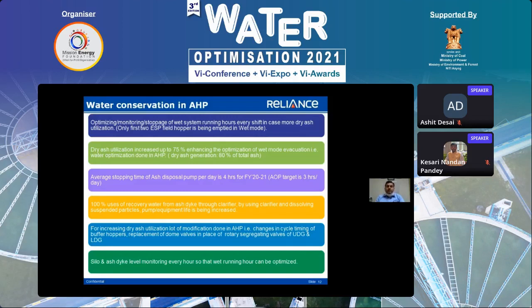But the silo is also 1.2 kilometer away, so we were facing numerous line pressurization problems in the dry line. So we made numerous line modifications. We have replaced 70 bends to cater to our situation. We have done a really remarkable job in the area of ash handling, so that our wet ash system is not being run, and we are running the ESP in completely dry mode. Our dry ash utilization is enhanced up to 75%.